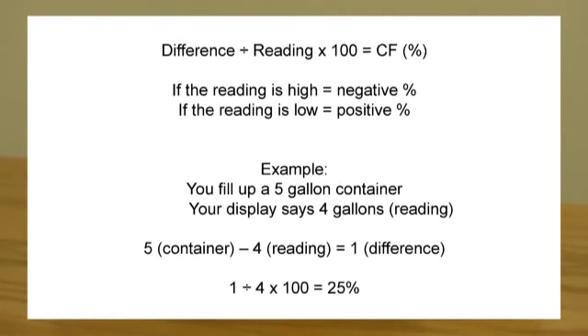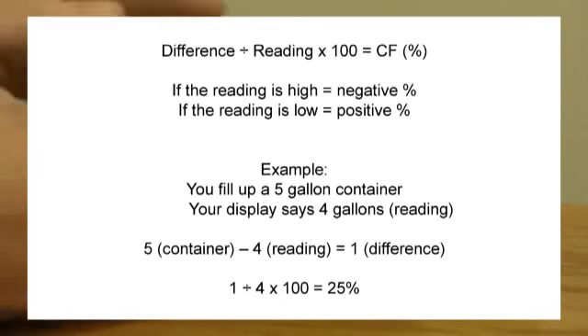So in that example I was talking about, you filled up a 5-gallon container, but the display only said 4 gallons. To do the math, you take the difference, so 5 gallons minus the 4 gallons, the difference is 1, and you divide that 1 by the reading, which was 4, and that gives you 0.25. You take that times 100, you get 25%. So what we're going to do is change this by 25%.